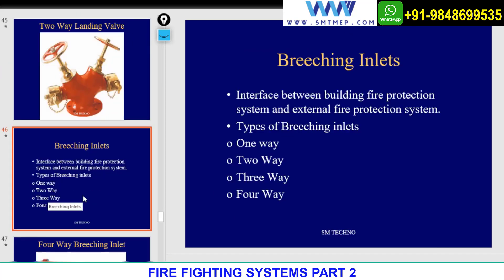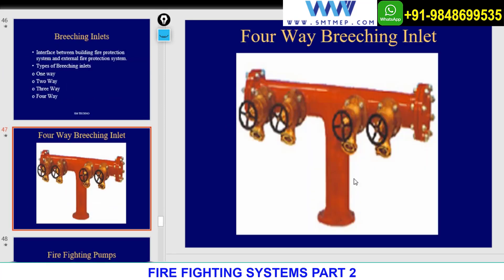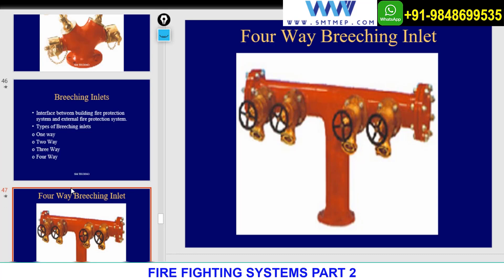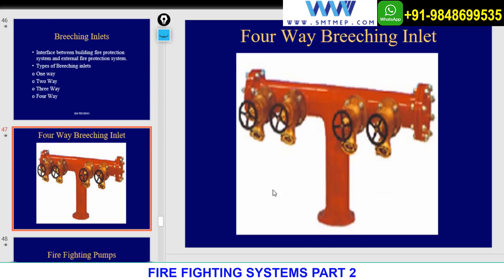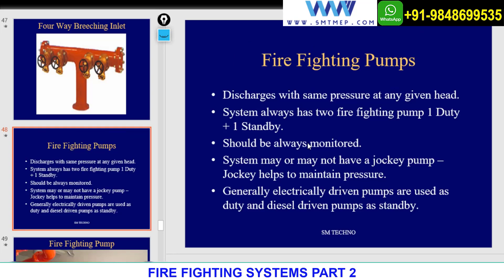The breaching inlet, also called a fire brigade connection or Siamese connection, is used to supply water to the building from a fire tanker. It allows water to enter the standpipe system or hose reel system. The fire brigade connects their pipe to the breaching inlet to supply water, and this pipe is referred to as a dry pipe. The installed systems — sprinkler, standpipe, etc. — are designed to control fire until the fire brigade arrives.